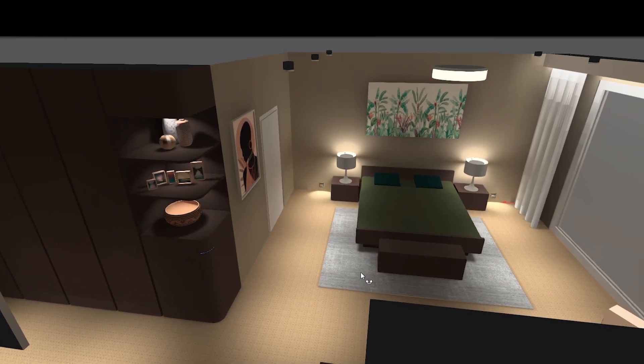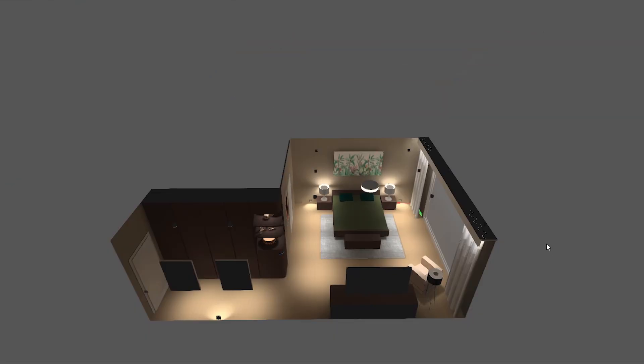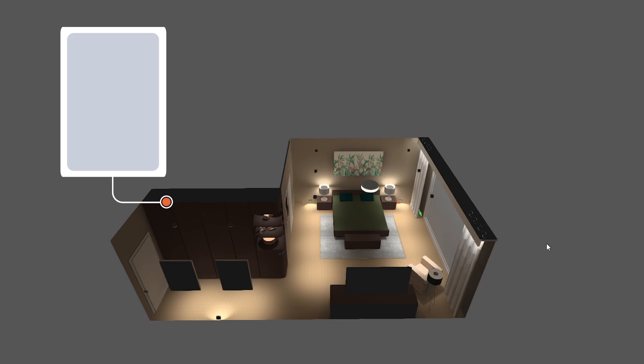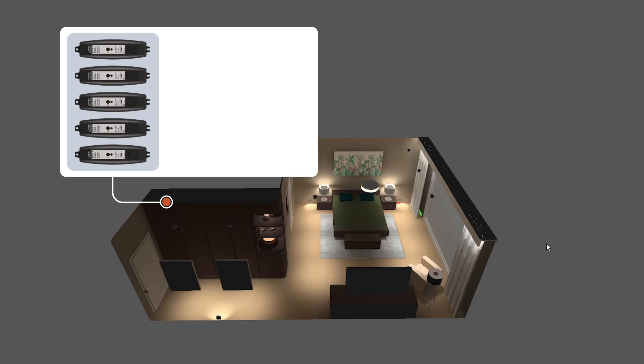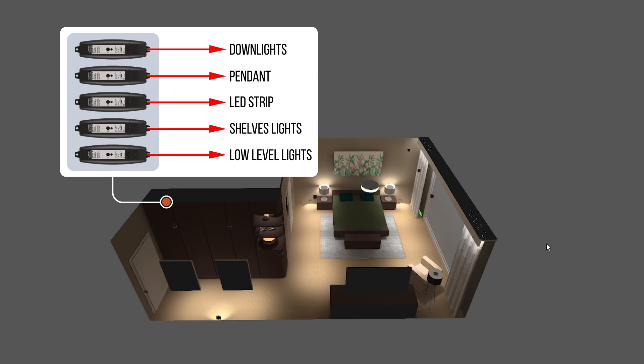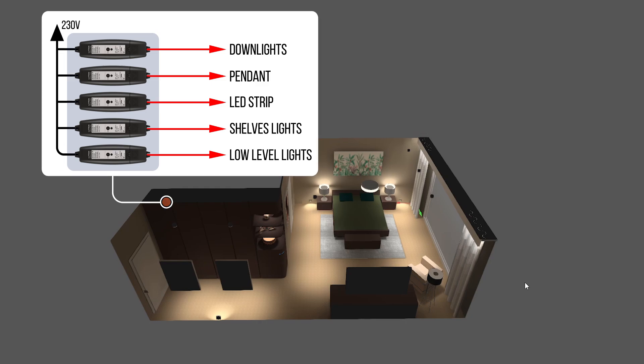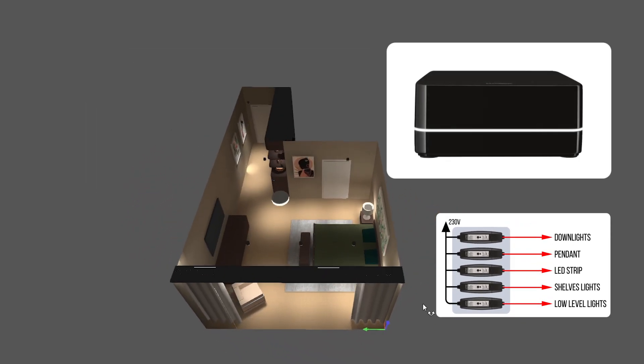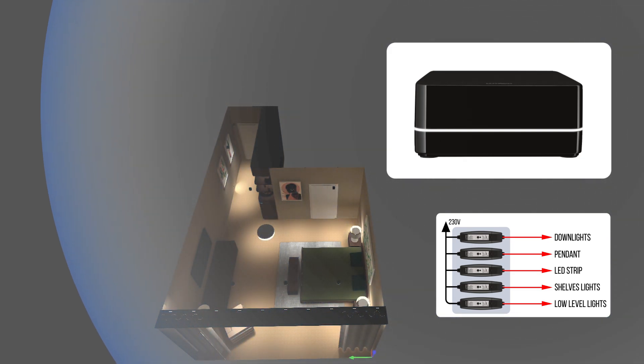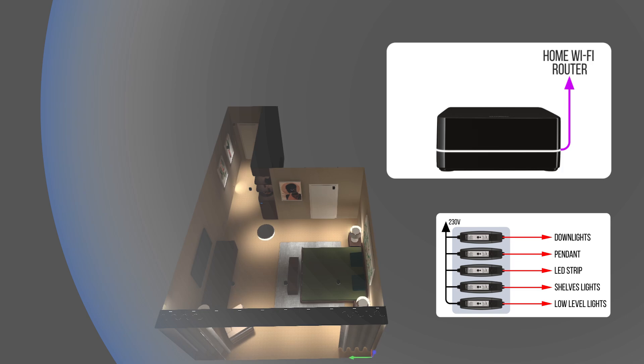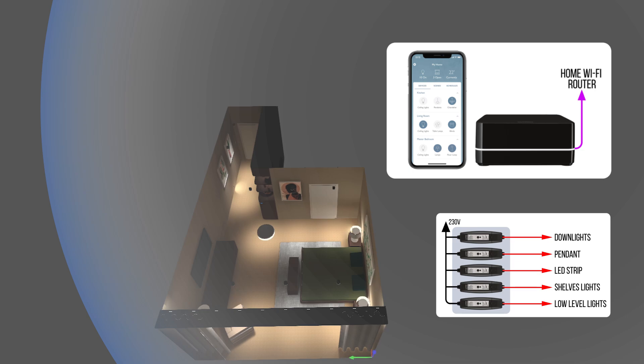Going back to our bedroom and the wiring of our Lutron RA2 Select. Let's say that somewhere at the back of my wardrobe, I will fit a small plastic enclosure that contains all my Lutron wireless inline dimmers. Each dimmer will be wired to its corresponding lighting circuit on one end — downlight, pendant, LED strip, etc. — and on the other end, they will be fed directly from my distribution panel, as you can see here. Next, I would have my Lutron RA2 Select main repeater fitted in the vicinity of my Lutron equipment. Remember, a single main repeater can control multiple rooms if you wish to. That repeater will have to be connected to your home Wi-Fi router to allow us to set up the system, program scenes, and for full control of your Lutron system from the Lutron app.